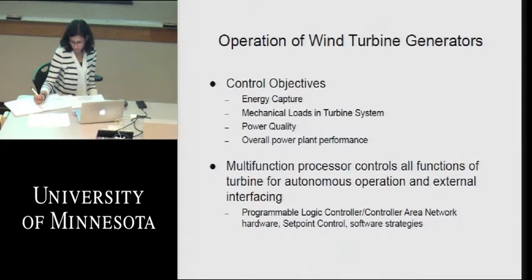The wind turbine by itself performs, but what the grid operator, what the power off-taker is concerned about is the overall power coming from the whole project, with all the wind turbines acting together in concert. So we want to use controls here, at the wind turbine level and at the park level, which we'll see here in a minute, to give us the best overall power plant performance and help us meet the interconnection requirements of the power off-taker, whether that's a utility district or a general city utility or a transmission company or a complete regional transmission provider.